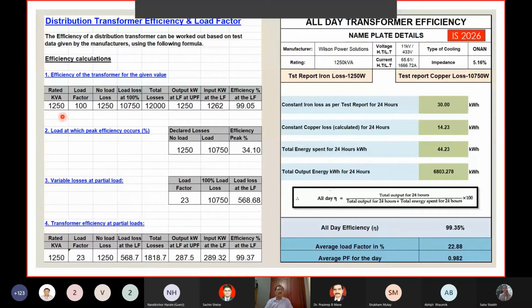Now I have another Excel here. You can ask for this Excel and take it for your working, where for the transformer with the declared losses, we have worked out what is the peak efficiency. The peak efficiency at rated load, 100% load, is 99.05%, whereas the maximum efficiency will occur for this transformer at 34% of the load, where these two losses are equal.